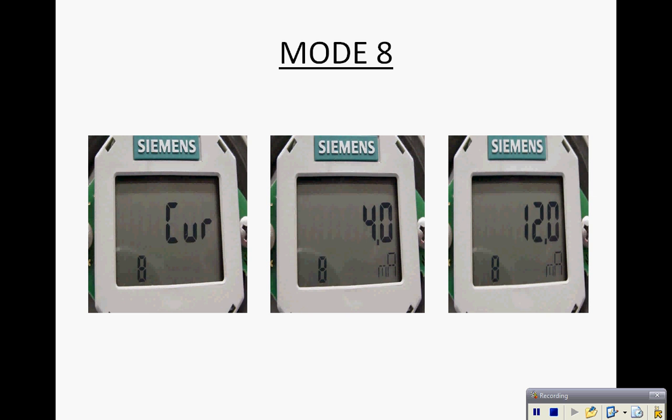Mode 8 is our loop checkout function. As you see we can drive the transmitter to 4 milliamps, 12 milliamps, 16 milliamps, 20 milliamps, etc.